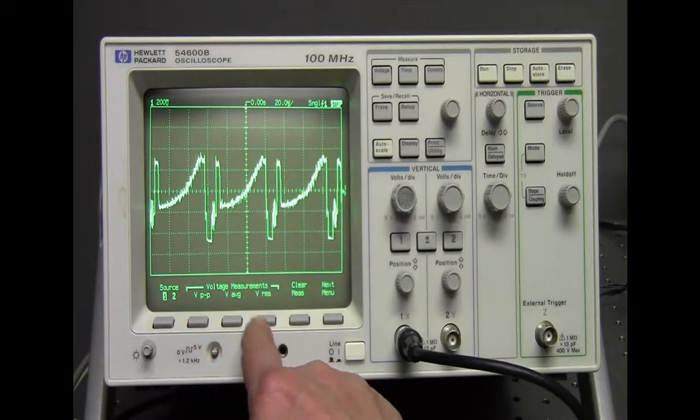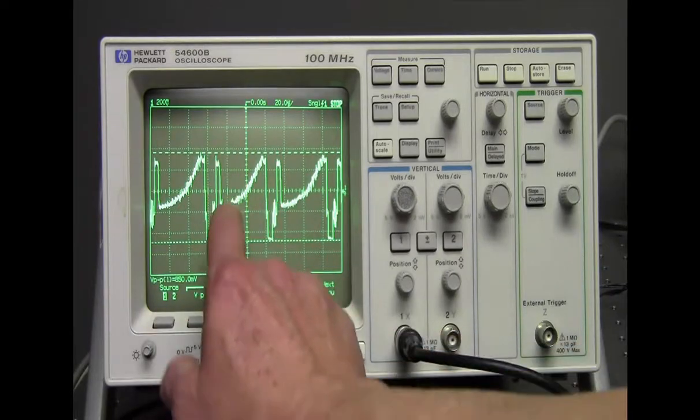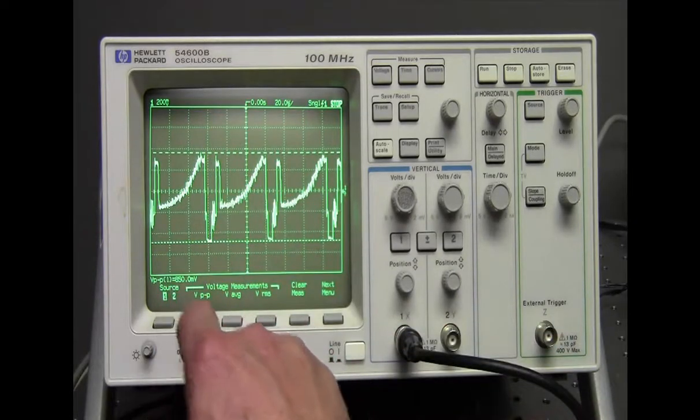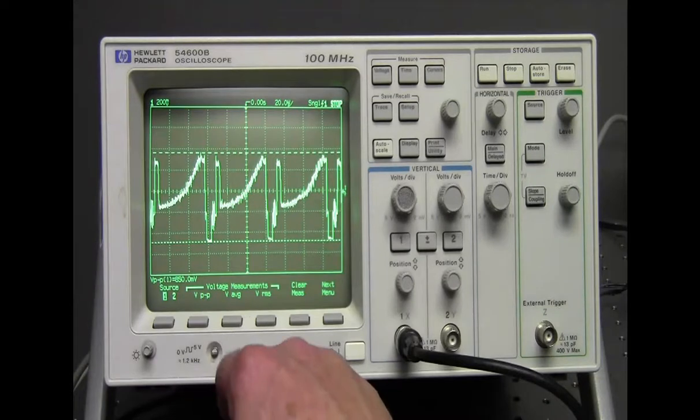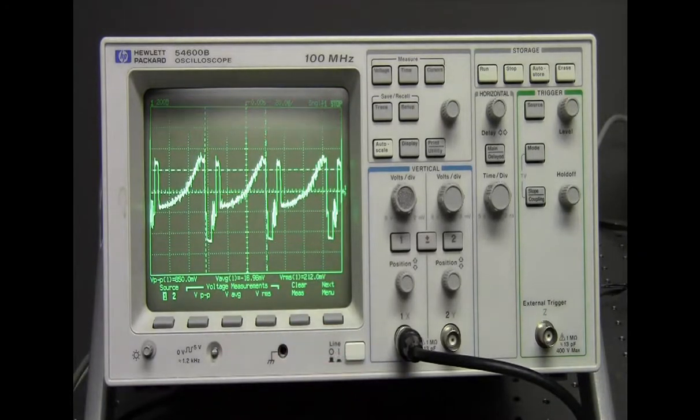This first one gives me the high and the low voltage reading. Here it says 850 millivolts. I can get voltage average and voltage RMS, and you would record the proper one that you need.